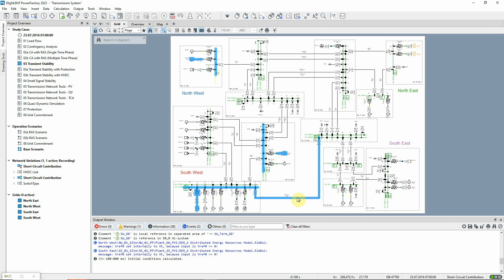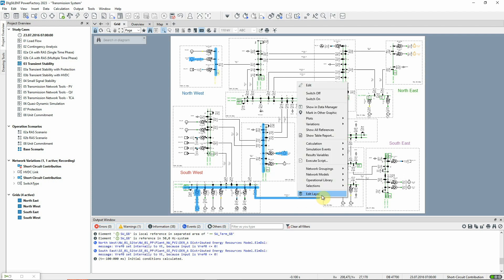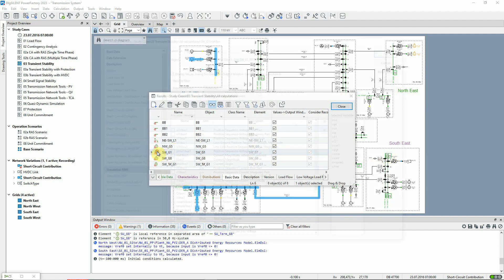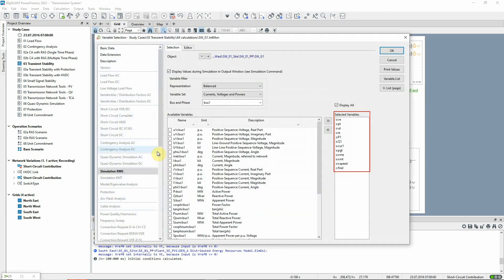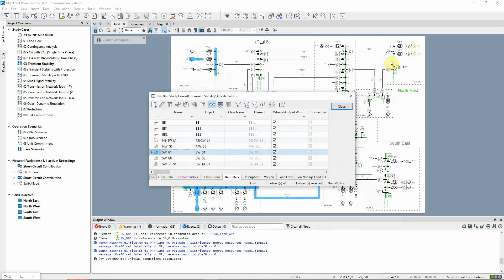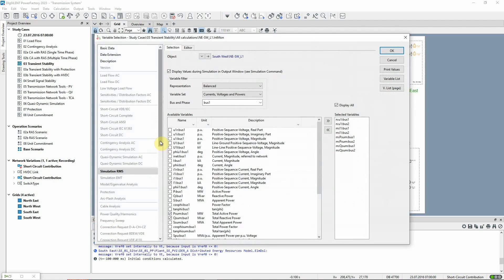In this case, we'll select a number of generators and other elements from the graphic, multi-selecting by holding down the control key. Then we right-click on one of the selected elements and choose Results, Variables, Simulation, RMS EMT. Default variables are already selected according to element class, but these selections can be changed. For example, for this line we can select the loading.